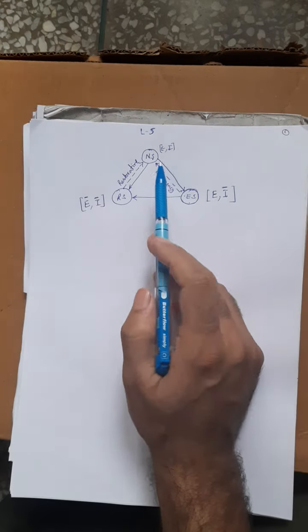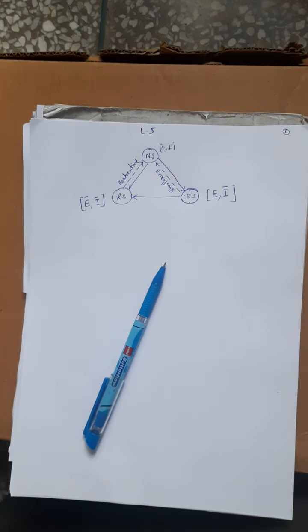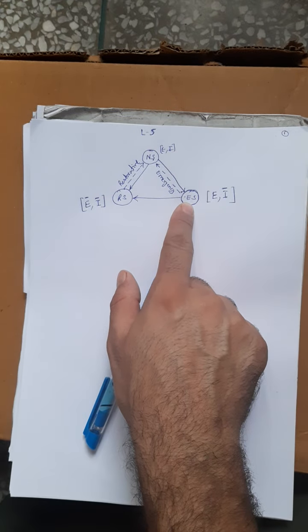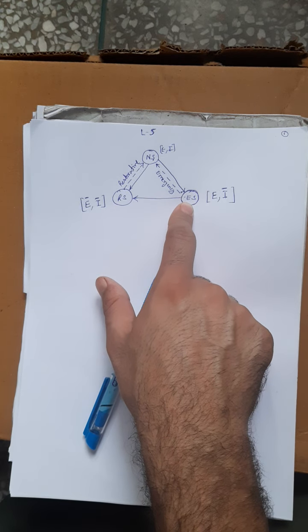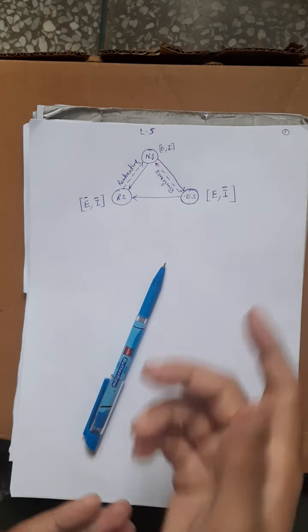This three-state model was later found to be insufficient because the system moves directly from normal to emergency state. It was thought that before the emergency state, an alert signal should go to the operator so that the operator can take some action to bring the system back to the normal state.